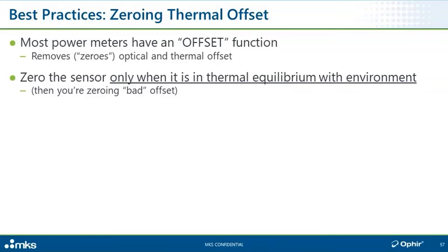Now, knowing that, a person may be tempted to press offset before turning on the laser and zeroing out that unwanted DC level. What's the problem with that? As the sensor continues to cool and approaches thermal equilibrium with the air in the lab, the actual thermal offset will get smaller and smaller. But if I press the offset button, my instrument is going to keep on subtracting that original offset from the reading, but that original offset is no longer really the offset.